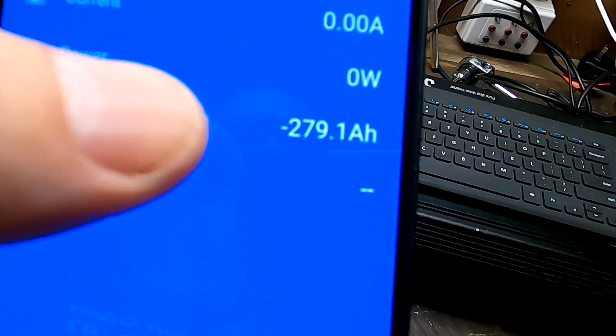We've already pulled 279 ampere hours from the battery, exactly the same capacity as the fake Hithium battery. We probably could have made another 0.1 or 0.2 ampere hours until the BMS shut off, but we're not getting 290 ampere hours out of the certified cells either. So far there's no difference between the capacity of the certified battery and the fake Hithium battery, same capacity, 100% the same.